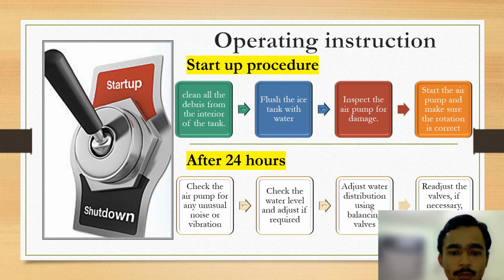So after 24 hours of operation, we must check the air pump for any unusual noise or vibration, because this noise or vibration might indicate damage in the component. And next step is to check the water level and adjust if required. Then adjust the water distribution using the balancing valve, and lastly readjust the valve if necessary.